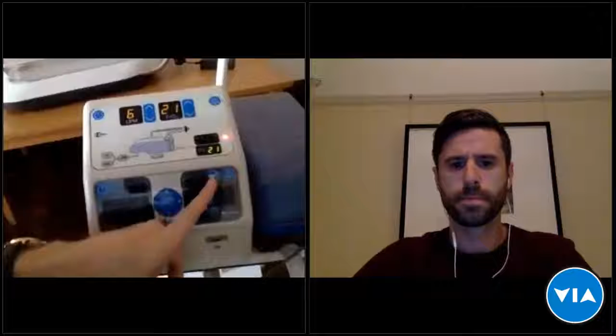The pulse oximeter has standard alarms for the heartbeat and the saturation level, higher and lower ranges of alarms. So it's very standard. These are the alarm ranges, these are the actual readings. Now obviously I'm not connected, so there's no sensor, but those are all the alarms. You can mute them, you can unmute them, but the momentary mute button only works for 2 minutes.